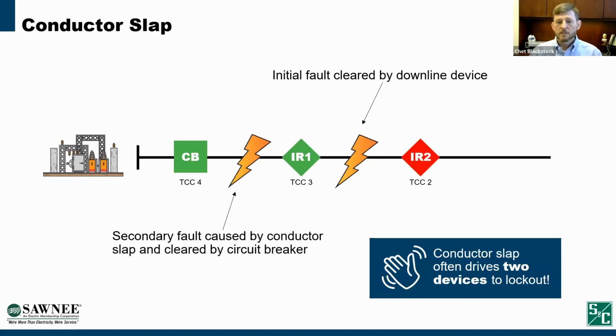So the other problem that we saw was conductor slap. To illustrate that, in this situation, we've got a fault that occurs downline of interrupter 1, and interrupter 1 clears that fault, but after it clears it, usually 1 to 2 seconds later, a secondary fault occurs between that device and the substation, where the phases come together, they touch and cause a secondary fault, causing your upline feeder breaker to operate.